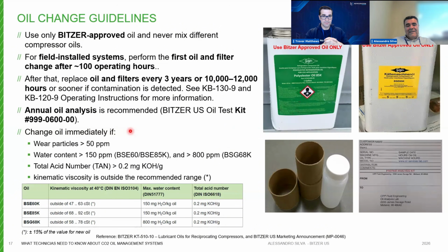Exactly. Yes. And here, in case you needed to send the parameters to a lab, we put together what we recommend. If any of these parameters exceed the recommended values, you have to change the oil immediately. For example, wear particles above 50 ppm, you have to change the oil.